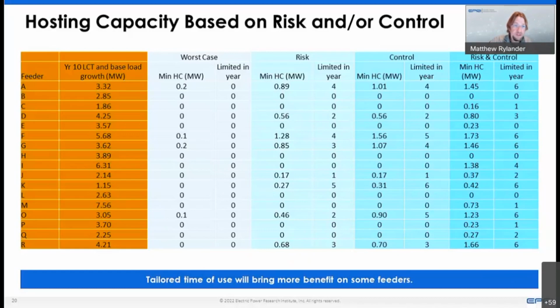This table focuses on worst-case conditions, but it also applies to better-off feeders. A feeder that can currently accommodate 1 megawatt might, with a little control, accommodate 2 to 3. You might not have any problems within the next 10-year horizon, and those feeders would no longer need immediate action. Or if action is needed, it's just that we need to actively manage or incentivize those resources to operate differently than they currently do.